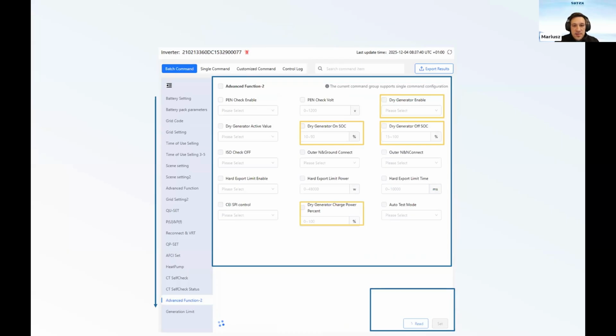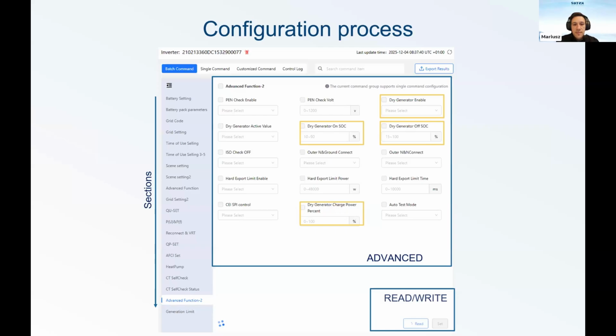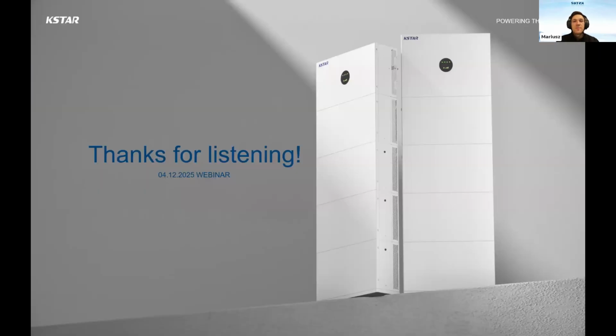And the last one is the settings for the diesel generator. We have the off SOC and on SOC. On SOC always needs to be lower than off SOC. We can also choose the diesel generator enable and the diesel generator power, just to avoid overload. And from the commissioning side, the settings side, and about the products, that was all from my perspective.